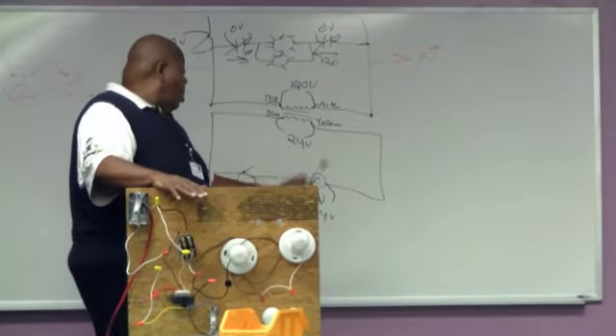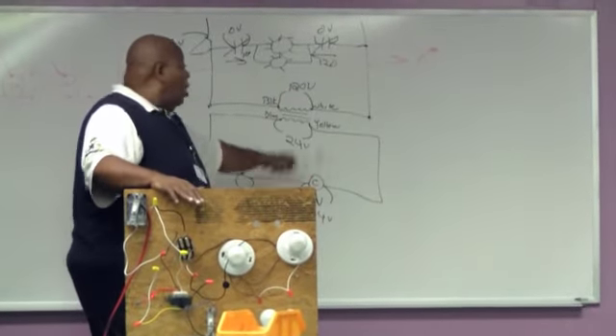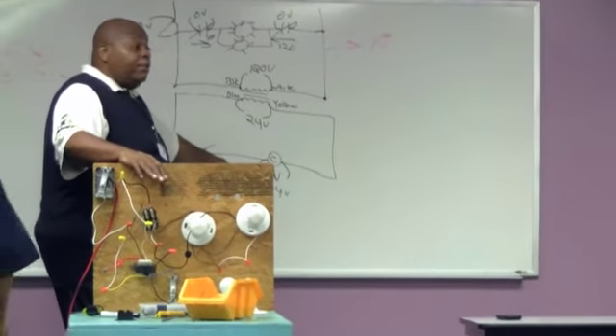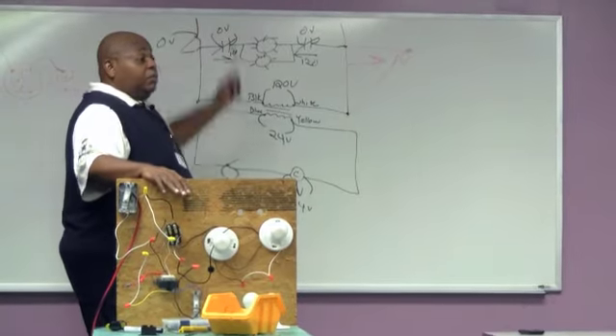Anytime you see a coil on this low side, we energize that coil, something has to happen up here. If nothing happens up here when you energize that coil, we know to start troubleshooting.